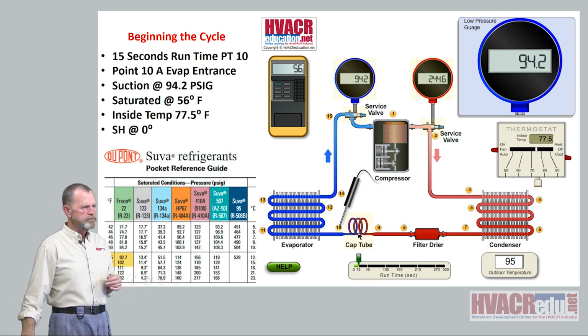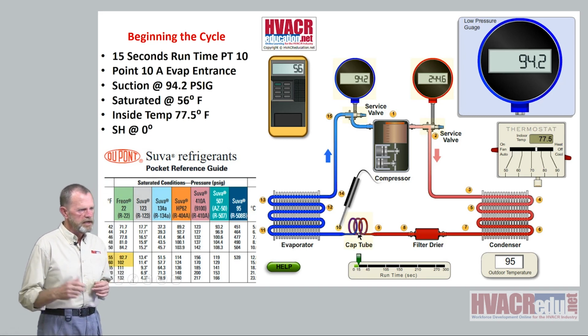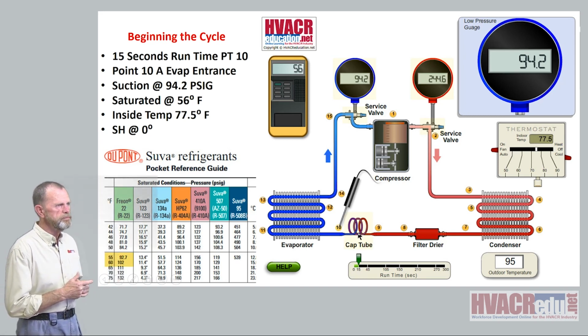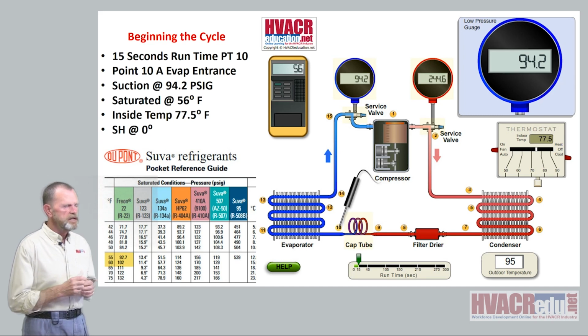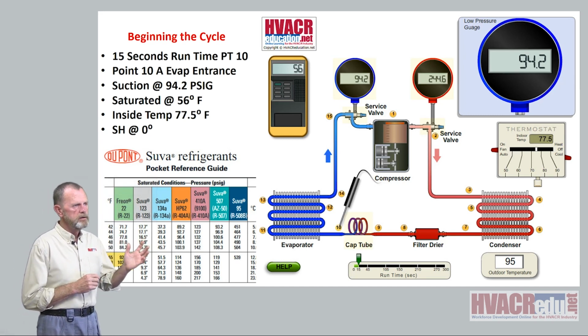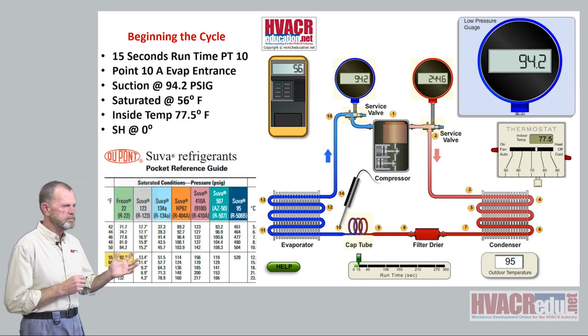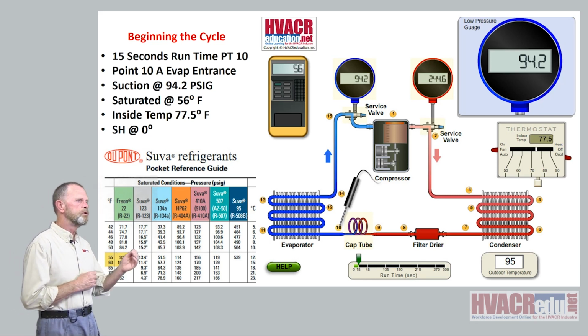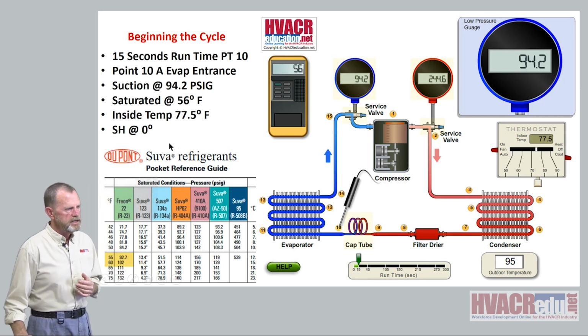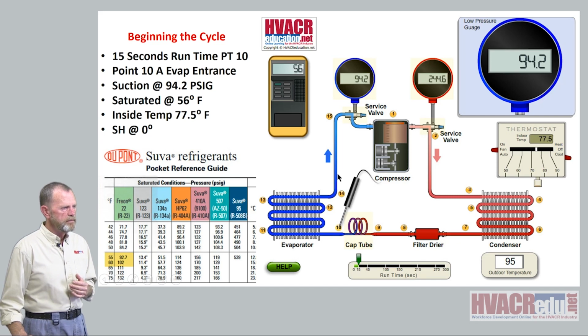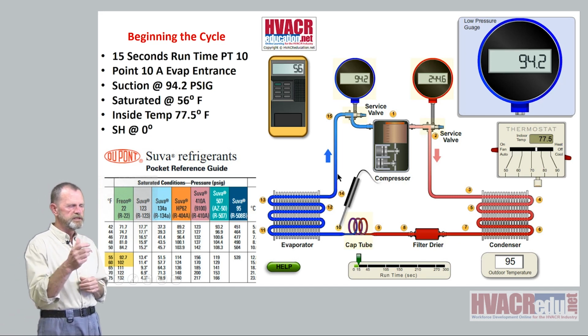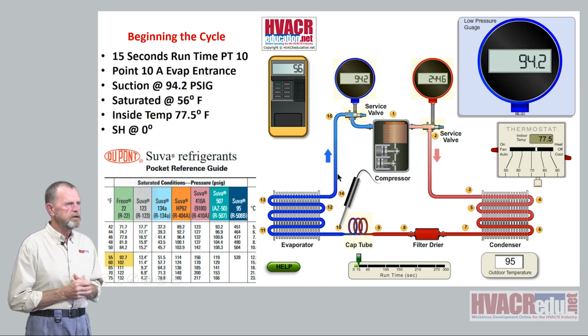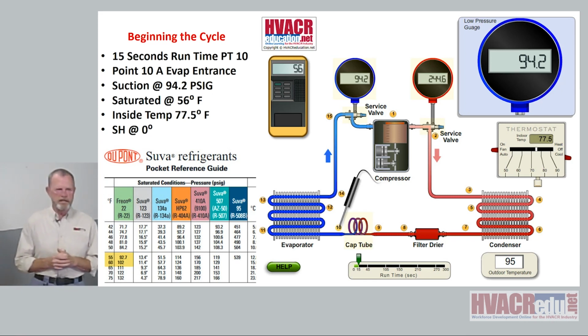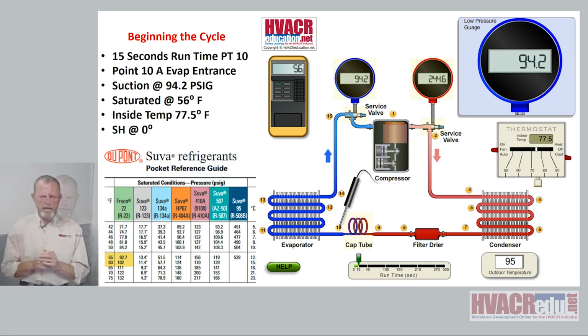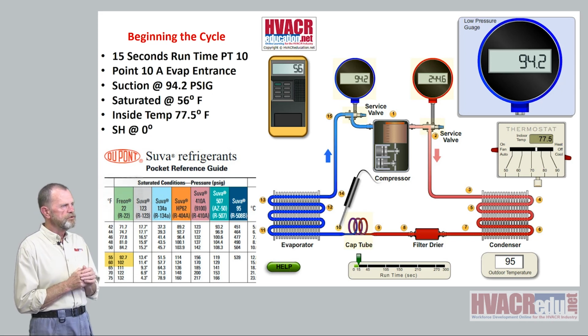Since we're in a capillary tube system, we're getting X amount of refrigerant through the metering device, and there's not really any way to throttle more in, like a thermal expansion valve or electronic expansion valve. They would be throttling more refrigerant in based on the exit temperature of the evaporator out here on the suction line. That's where the sensing bulb for the thermal expansion valve is clamped, and also where the sensor for an electronic expansion valve goes, on the outlet of the evaporator. But we're dealing with a cap tube, all right? So let's run through this.